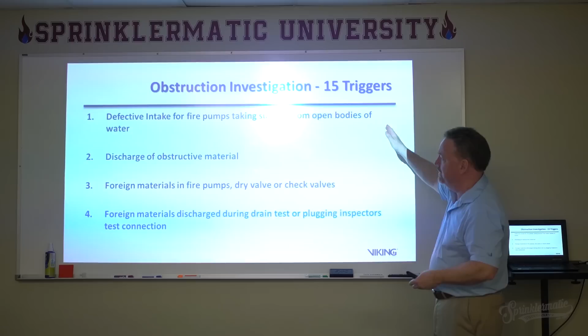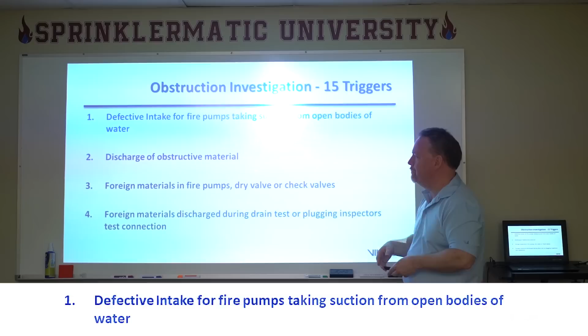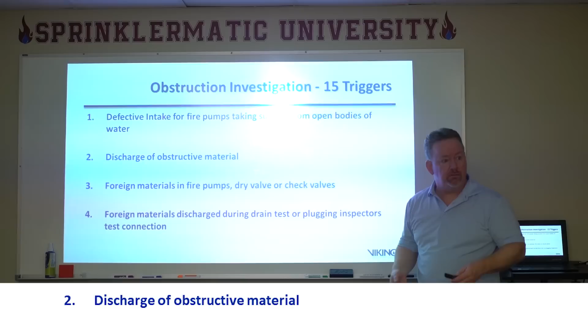If you have a defective intake for the fire pumps that are taking water from an open pond or a raw water source, they're supposed to go through these filters. If you've got a defective filter, you're going to do an obstruction investigation. If you find, in the inspection, discharge of any obstructive material. If I'm running a 2-inch main drain test, all of a sudden I get something coming out, rocks, something, coming out of my discharge, we're going to do an obstruction investigation. Foreign materials in fire pumps and dry valves and check valves. Boy, you're going to know it if you've got a foreign material in your fire pump real quick. It's going to grind to a halt, or it's going to make a heck of a lot of noise. All right, so if you've got that, then you've got issues and you're going to do that.